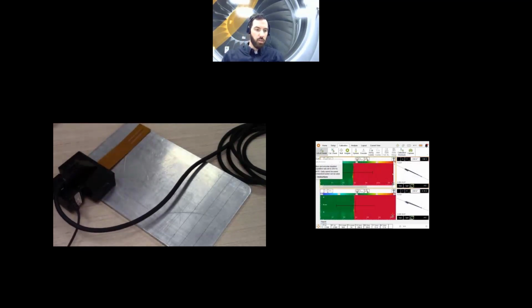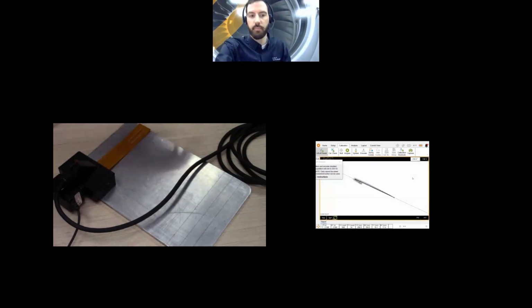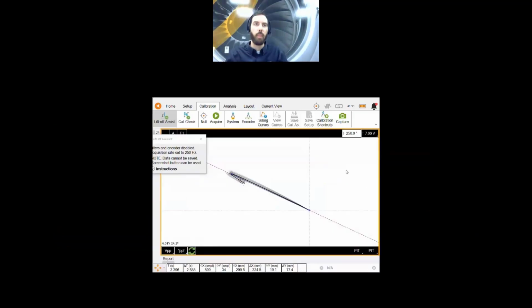So if we have a closer look at this shape of the liftoff signal, let me switch back to the full view. What you see here is that it is a very usual shape of signal. We have a very straight line with a hook at the tip that corresponds to a transmit-receive topology, which is what our probe is using here. So the idea of the liftoff calibration, as always, is to bring this curve to the horizontal, pointing to the left, like this.